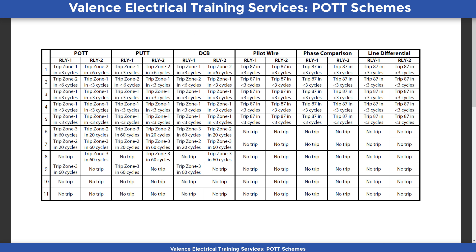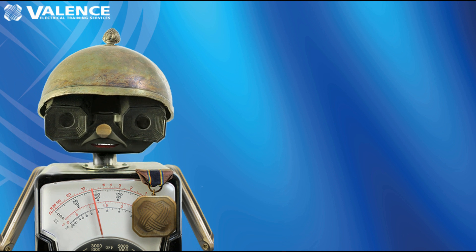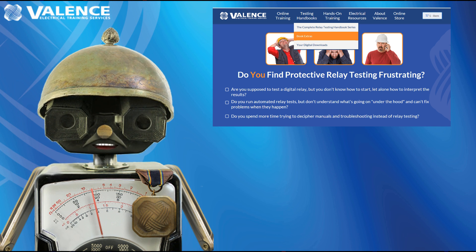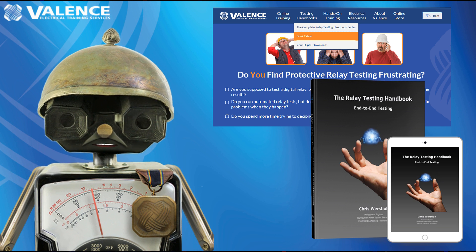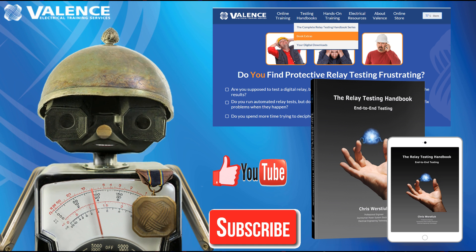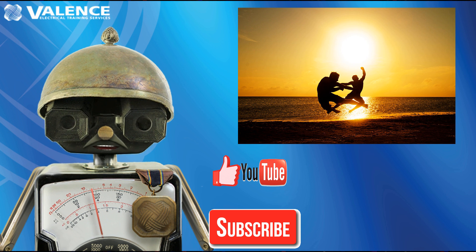The dirty little secret of communication-assisted trip schemes is that they all have the same operating characteristics under normal operating conditions. All end-to-end tests should be performed on either side of each protected zone to make sure the protected line is isolated faster when a communication trip scheme is applied. However, POTT schemes require additional tests that prove that the Zone 3 timer is appropriate to the application by simulating a current reversal from both directions. Thanks for watching this video. You can play with the animation and more by following the link on the screen, or get more information about testing these schemes in the Relay Testing Handbook, End-to-End Testing. Please like this video and subscribe to our channel to help us keep providing free content with no ads. And don't forget to have fun out there.